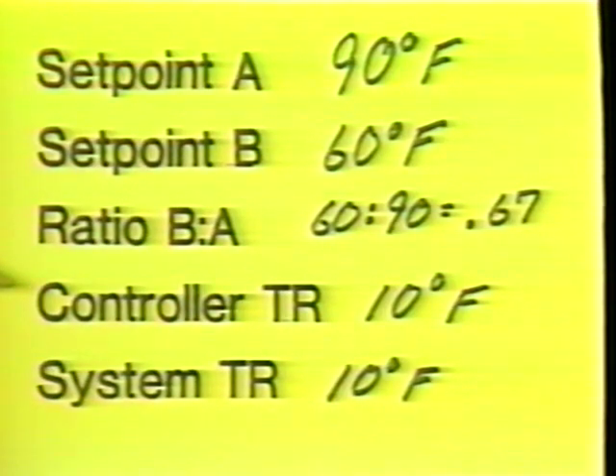Controller throttling range. What the actual controller throttling range should be will be determined by the actual equipment and cannot be determined beforehand. However, a general rule of thumb is 10 degrees throttling range for smaller hot water systems, and 20 degrees for larger systems, which will respond more slowly.